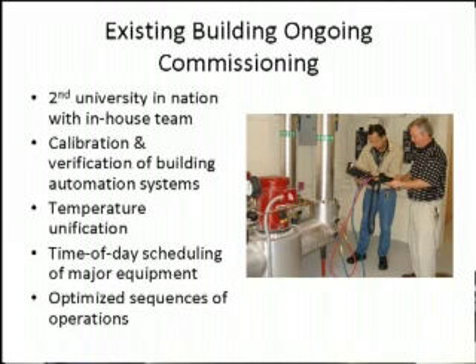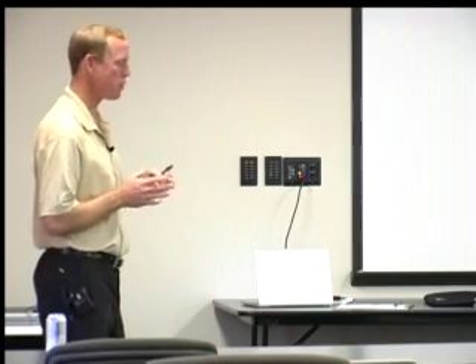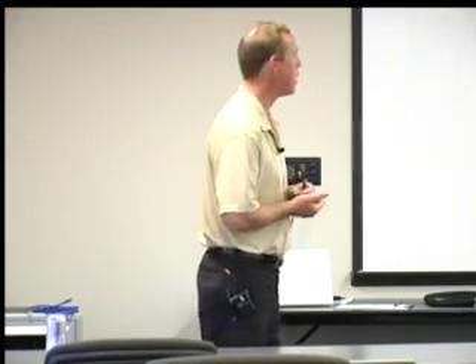But these guys go in, and these are actually two technicians calibrating a pump maybe, and the sensors associated with it, to make sure that the computer is getting the right inputs. The next thing they really focus on is temperature unification. So in these multi-zone systems that we have and you have in many of your facilities, you can very easily have simultaneous heating and cooling taking place in two adjacent spaces that are sharing the air. And so as you can imagine, that's super energy intensive. So I talked earlier about that policy.